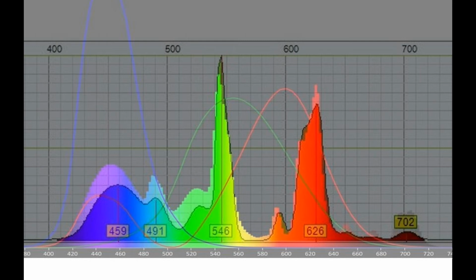The weakness in the i-Phos is in the relative intensities of the wavelengths, and we do see some disagreements between the high peaks and some of the smaller peaks. And this is inevitably due to the fact that the webcam sensor that we're using here, that gives us the big cost advantage, is not very linear. It's not designed to do this, and so it doesn't do it as well as the high-end instruments. Nevertheless, the i-Phos did all the work necessary to diagnose the problem that Patrick needed solving.